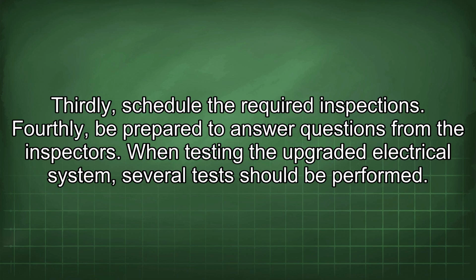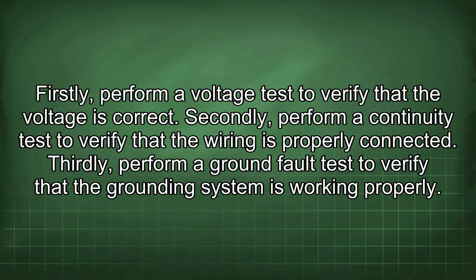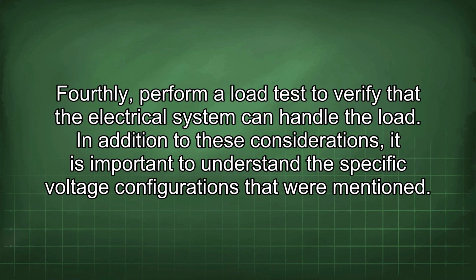When testing the upgraded electrical system, several tests should be performed: a voltage test to verify the voltage is correct, a continuity test to verify the wiring is properly connected, a ground fault test to verify the grounding system is working properly, and a load test to verify the electrical system can handle the load.